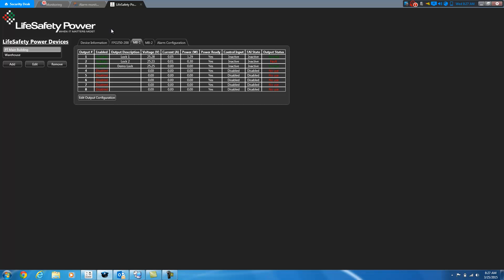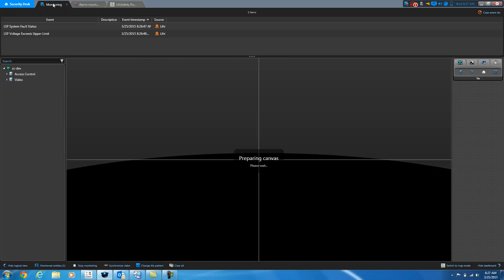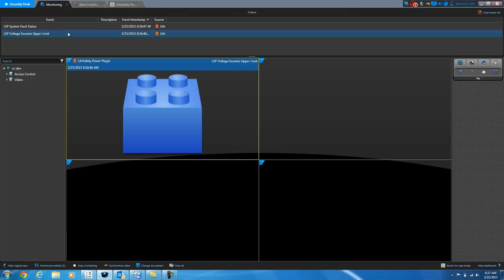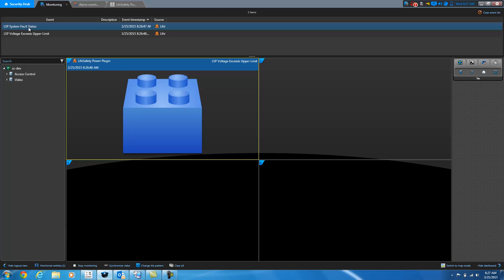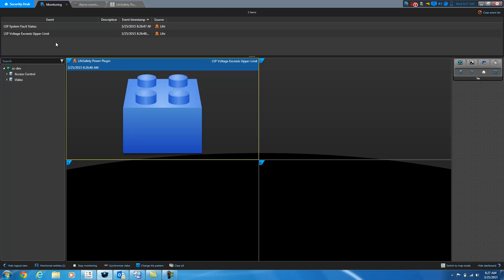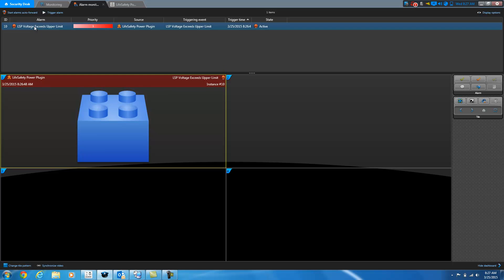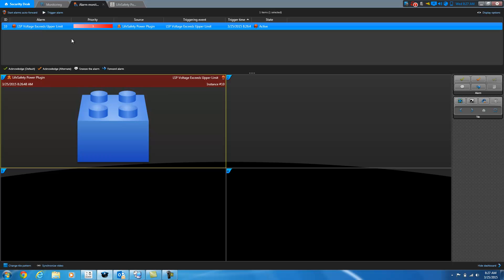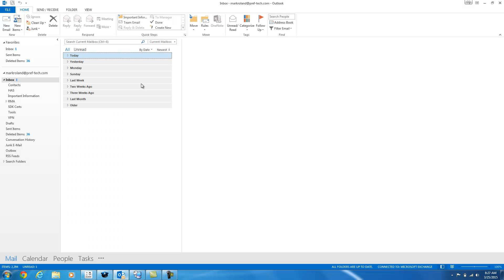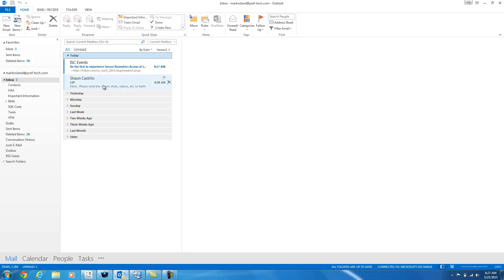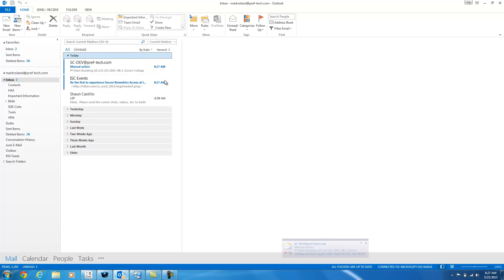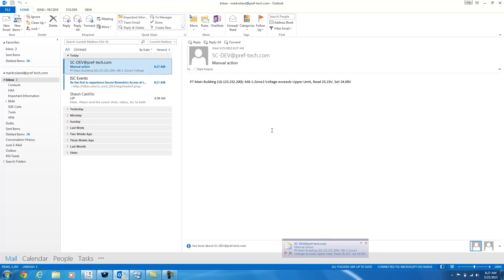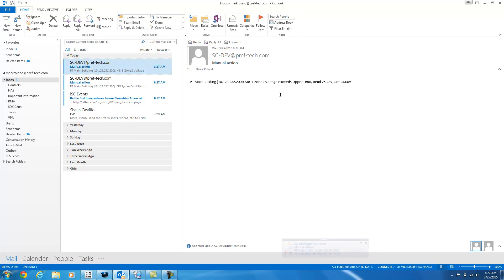When I did that, a couple of things happened. I got a fault status event, and a voltage exceeds upper limit event. And then because I had Genetec configured to raise an alarm when the voltage exceeds the upper limit, I also got an alarm here. And I also received an email telling me that the voltage exceeded the upper limit.